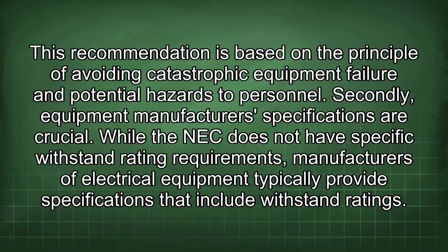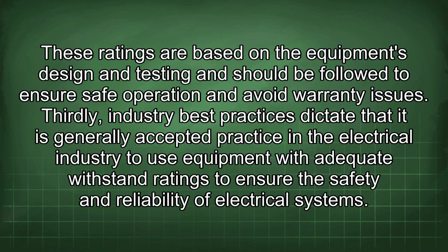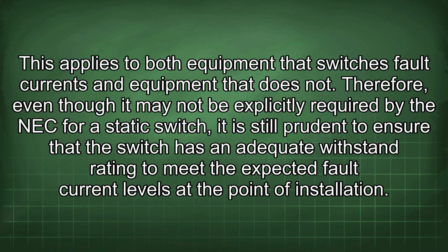Secondly, equipment manufacturer specifications are crucial. While the NEC does not have specific withstand rating requirements, manufacturers of electrical equipment typically provide specifications that include withstand ratings. These ratings are based on the equipment's design and testing and should be followed to ensure safe operation and avoid warranty issues. Thirdly, industry best practices dictate that it is generally accepted practice in the electrical industry to use equipment with adequate withstand ratings to ensure the safety and reliability of electrical systems. This applies to both equipment that switches fault currents and equipment that does not.